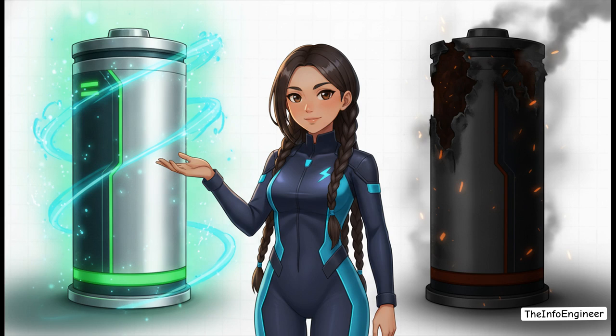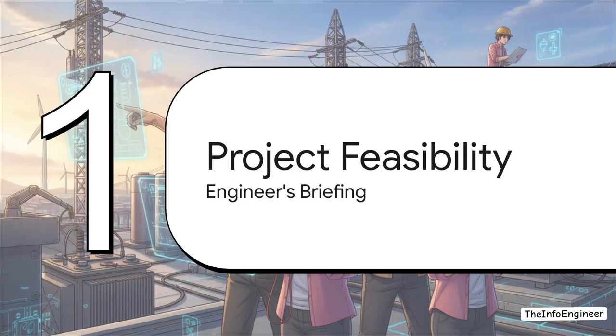The absolute secret to preserving your wildly expensive battery bank is strict depth of discharge, or DoD management. Listen, if you drain your batteries completely flat every single night, you will destroy them. By engineering your storage capacity so you're only cycling between 10 to 60% of their capacity daily, you will drastically extend their operational lifespan. Finally, Section 6, our project feasibility summary, the engineer's final briefing.